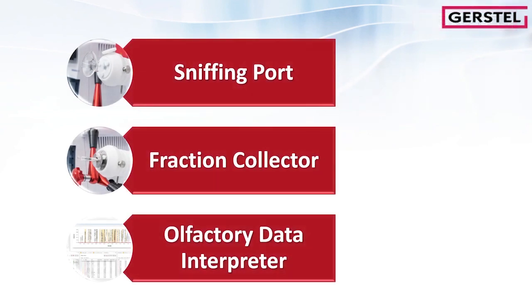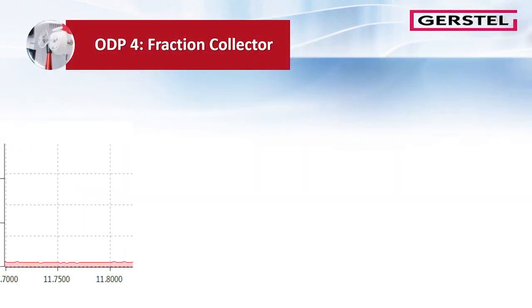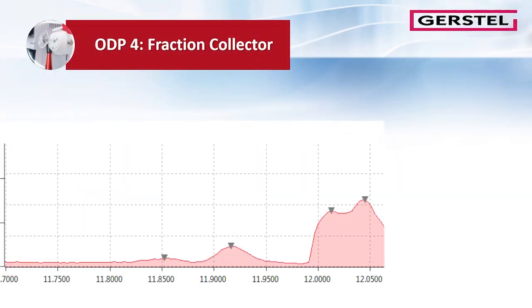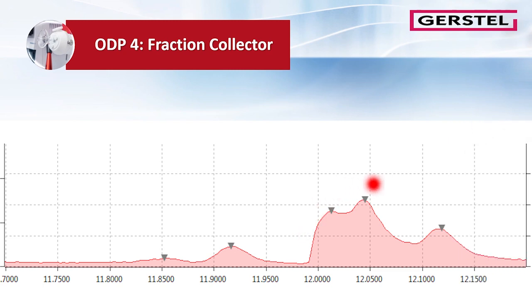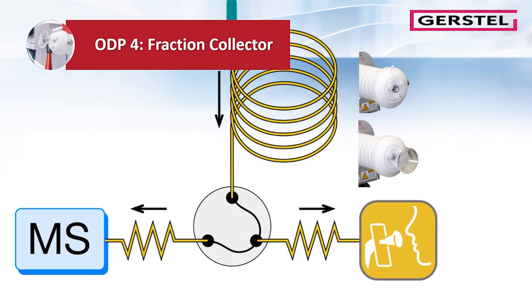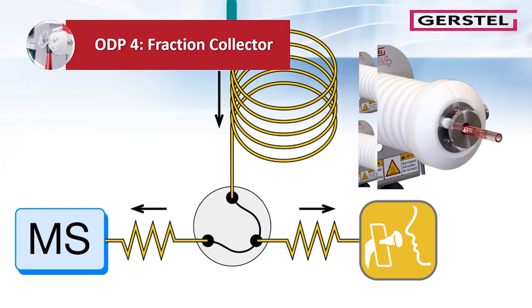In the next section, we talk about the fraction collector. The sniff and trap function allows eluent collection at any retention time, with easy installation of the Sorbent tube — just plug and trap. In this chromatogram, you see three coeluting peaks at the right-hand side. With a small modification of the ODP-4, we convert it to a fraction collector.